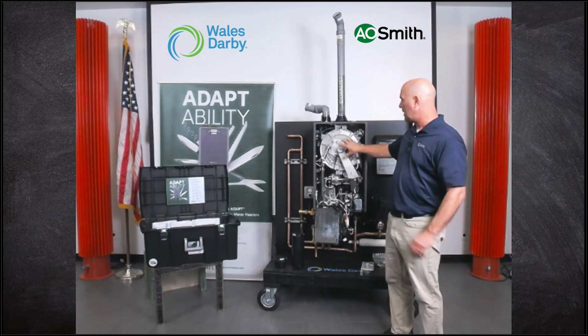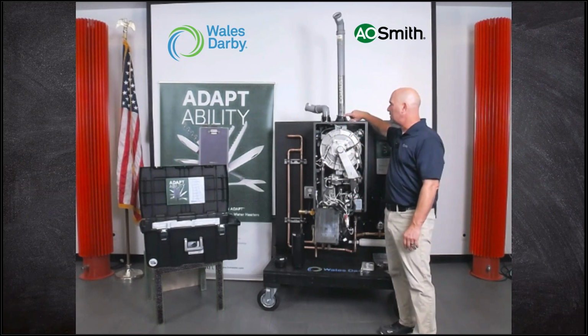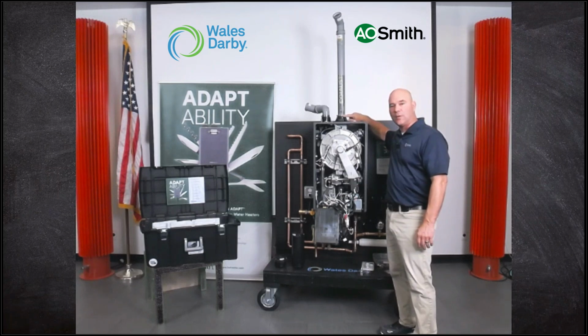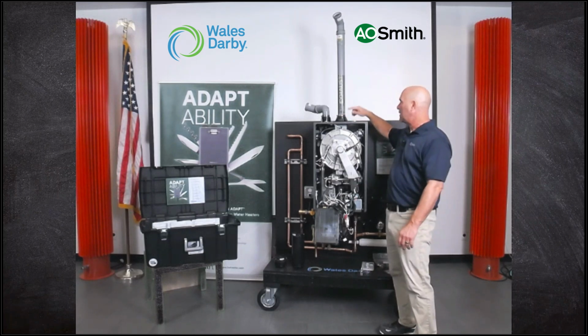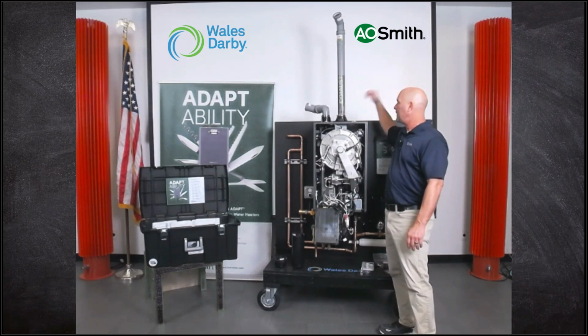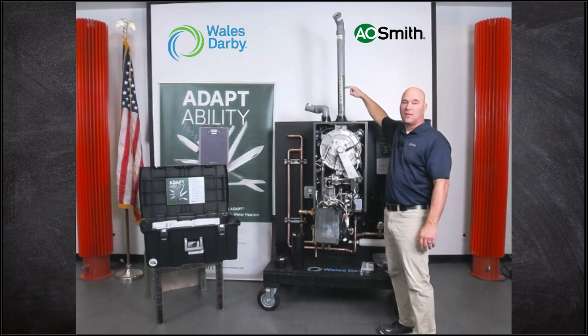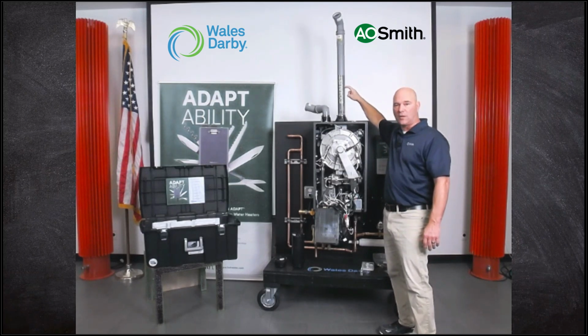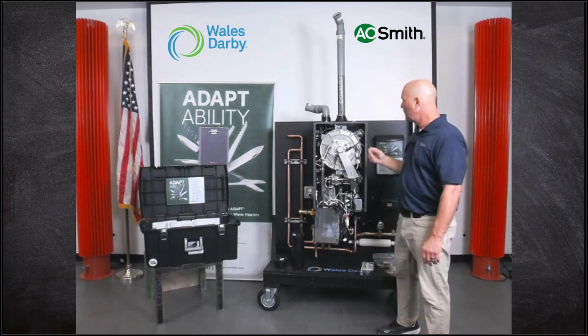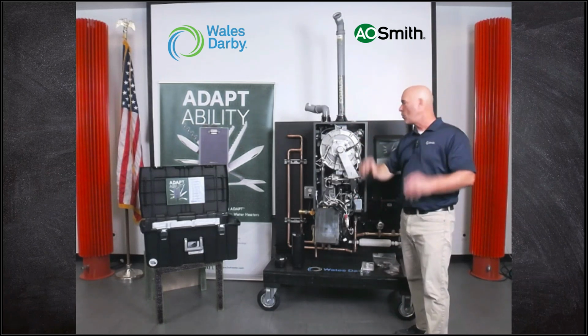With these new heat exchangers, we were able to change our venting. It used to be 3-inch. Now we can do 2-inch up to 75 feet, and we can do 3-inch up to 150 feet. You just have to make the transition within the first 12 inches to the 3-inch pipe if you want to go the full 150 feet. So be aware of that. Always use long sweep elbows.